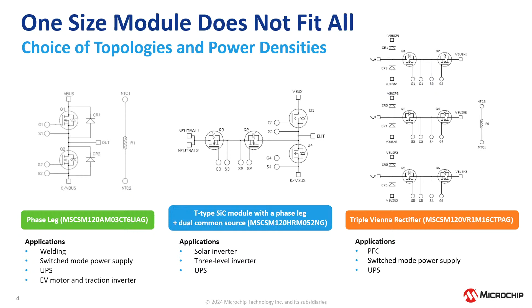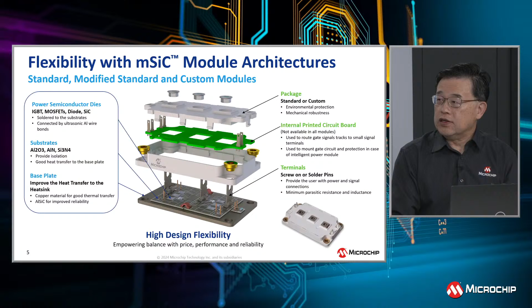Once the module is settled on, our standard products should be a starting point for customers. Quite often one size does not fit all, and there's a need to tweak the module. So we offer customization at both substrate and base plate levels, to maximize thermal conductivity and throughput, protect the module, and maximize performance and longevity. You balance that effect by mixing the substrate material against the right base plate material. All this comes in our module topologies with optional PCB to terminate traces and signaling. It's a flexible customization scheme that's there if customers need it.